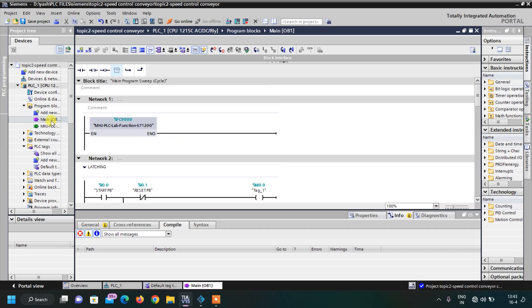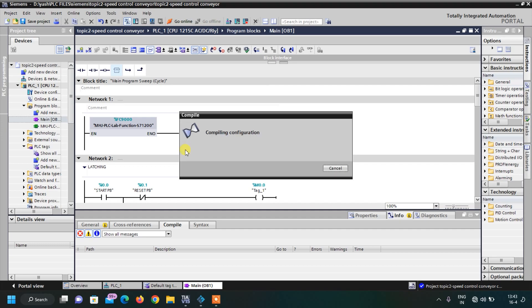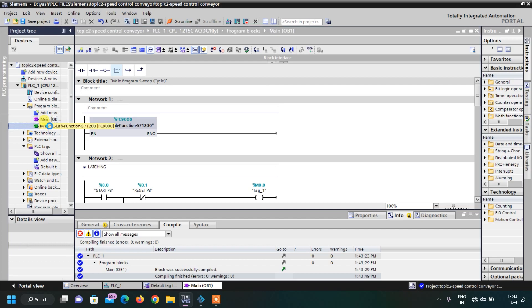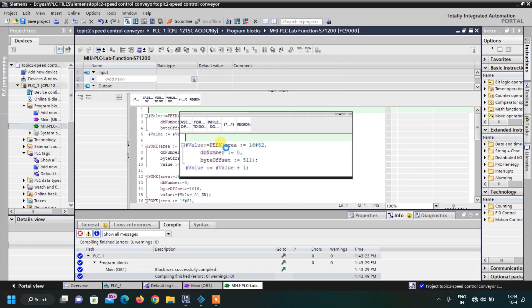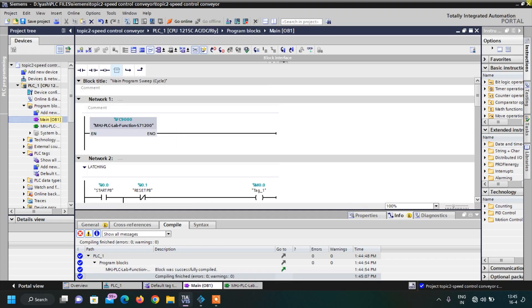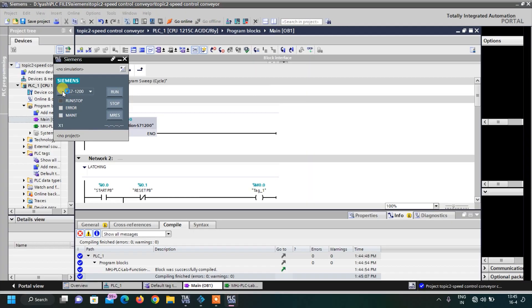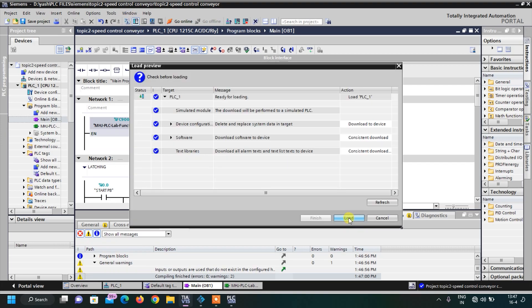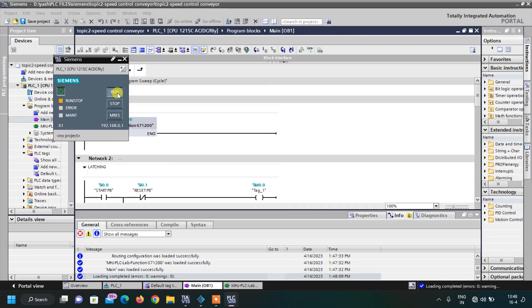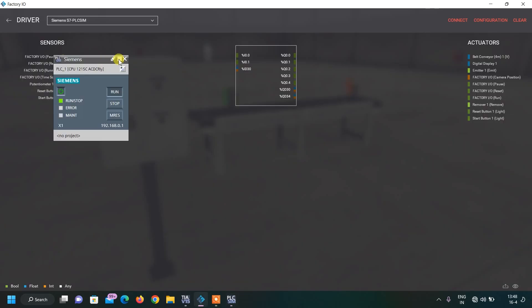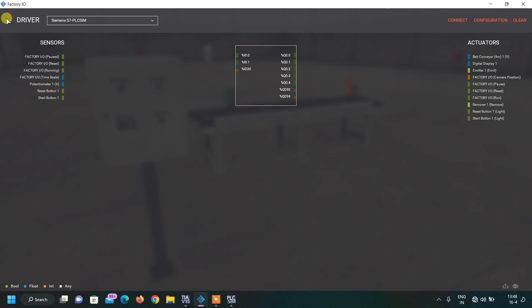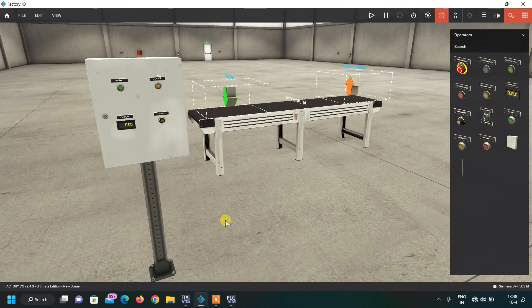Now let us compile. We compile Main OB1 first, and then similarly compile the function block by double-clicking on it. Then open Main OB1 again, minimize, and open the PLC simulator. Turn on the simulator and download our project to it using the load icon. Open PLC Sim again and click Run on the CPU.